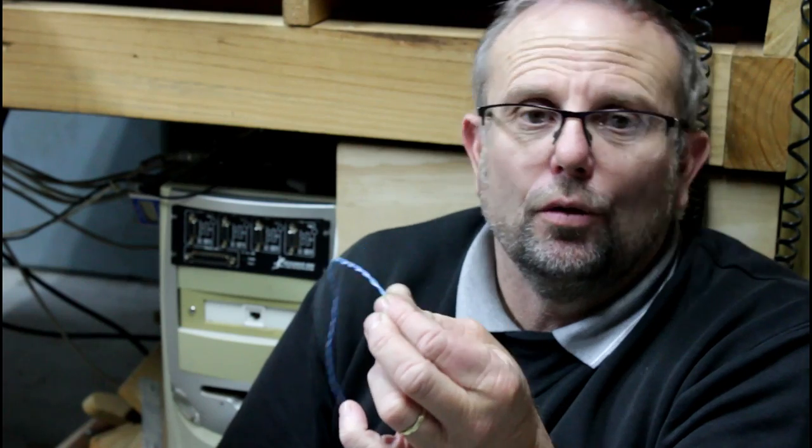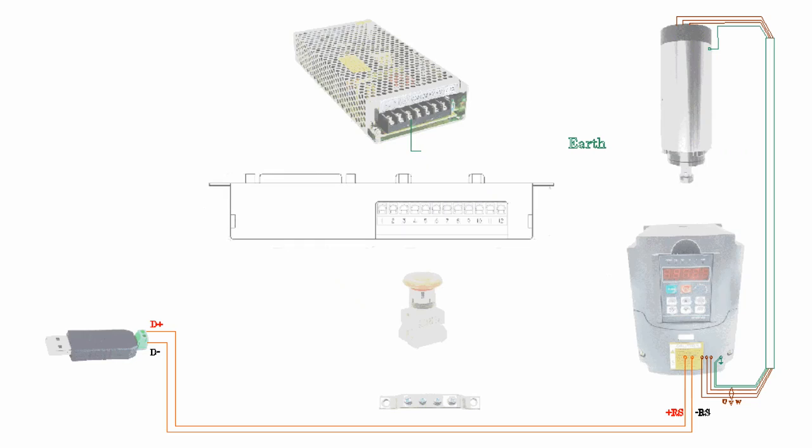In theory it doesn't actually need to be shielded but it's not really going to hurt. The important thing is if you're going to use a shielded cable, don't use one that has an outer shield and a single wire in it, you need one with two wires on the inside and then you can just ground that outside shield to help.